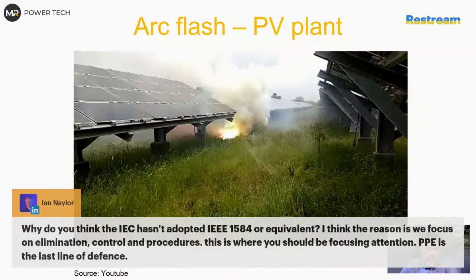And that's the point. It's not that we always go with PPE, because I always do a lot of other things before. The idea is that you need to go with PPE at some point, but instead of going with 40 calories, after all the changes you go with 4 or 8 calories, which is generally what I'm wearing now. So that's the idea behind it. But it would be nice if someone came up with proper rules adopted in IEC, and we wouldn't have to really go around this.